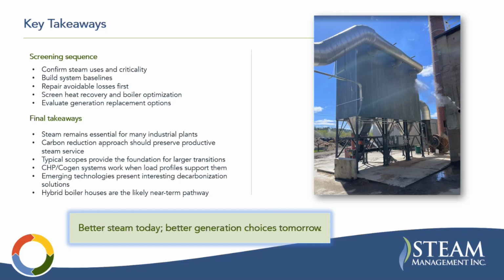Somebody says if the heat return is... oh, I already answered that one. Does steam leave the steam turbine? We talked about that. Somebody said it's usually only saturated for condensing steam turbines and back pressure turbines. Okay, great. For large steam systems, do you recommend monitoring all steam traps or only critical and high loss traps? And what criteria do you normally use to decide which traps should be continuously monitored?